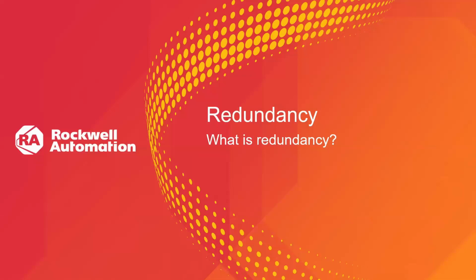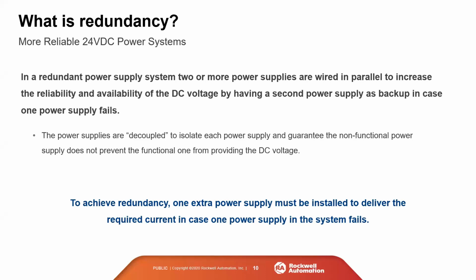What is redundancy, and why do we need redundancy in our system? In a redundant power supply system, 2 or more power supplies are wired in parallel to increase reliability and availability of the DC voltage. You have the second power supply as a backup, just in case one power supply fails. So you'll typically see this as a 1+1 or an N+1 type of system, and we'll spend further time in upcoming slides on what that means.